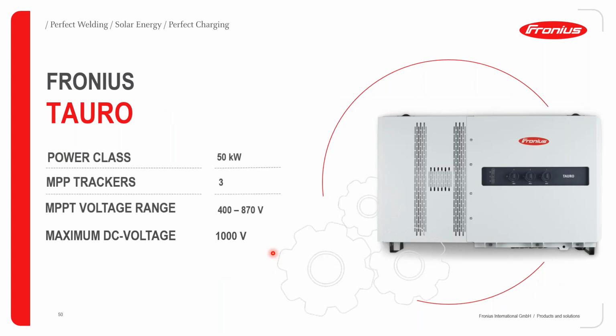For our Fronius Tauro, this is our normal version. It's only available in the 50 kilowatt power range, has 3 MPPT trackers, and the MPPT voltage range is from 400 to 870 volts, with a maximum DC voltage again of 1000 volts. Its weight is also 74 kilograms.